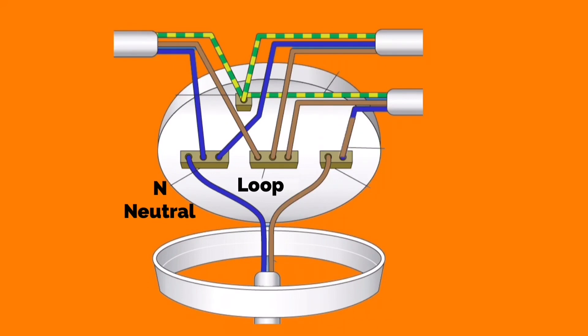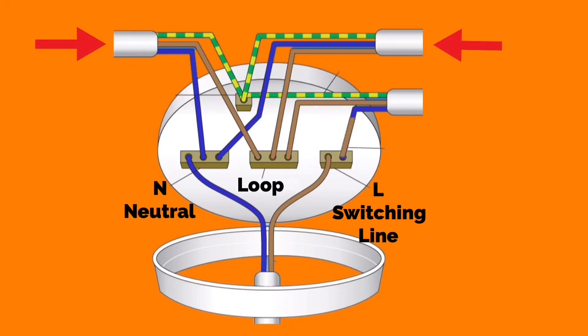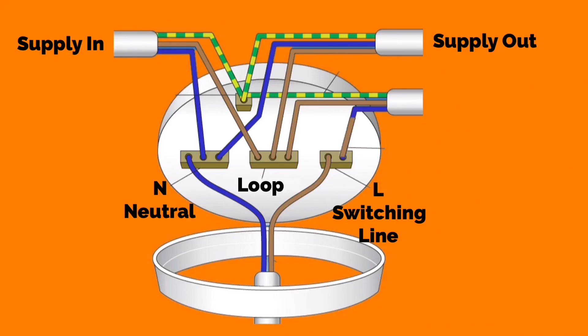The far right hand side is usually identified with the letter L but is actually a switching line conductor - the one that gives you control over the lamp by turning it on and off. Looking at the top two cables, both left and right hand side, they are the supply coming in and the supply going out. The left hand side is the supply coming in and the right takes the supply into another room.